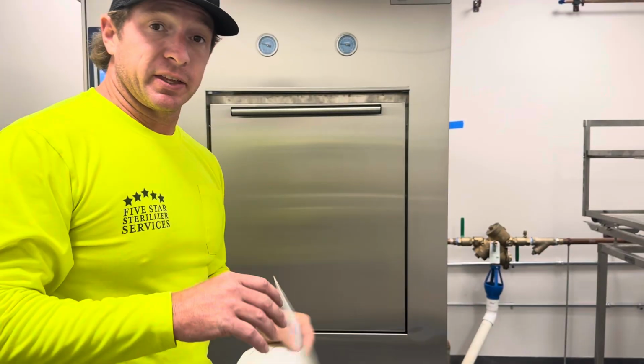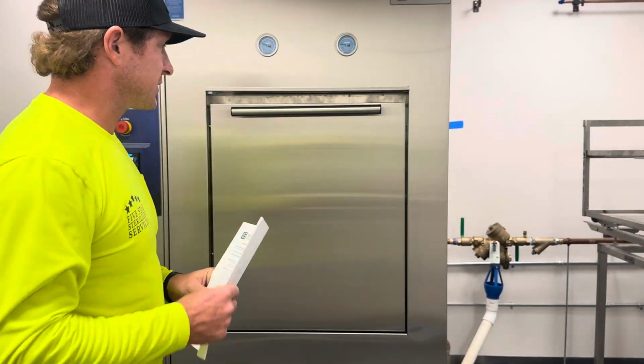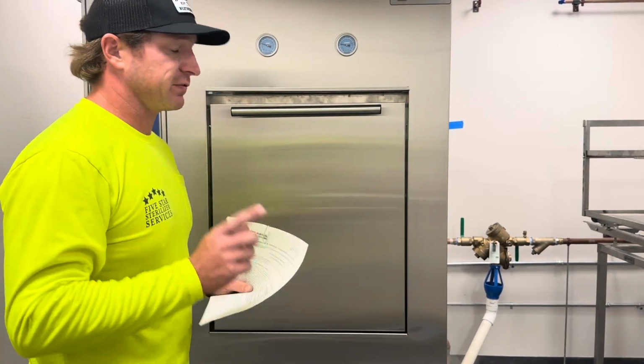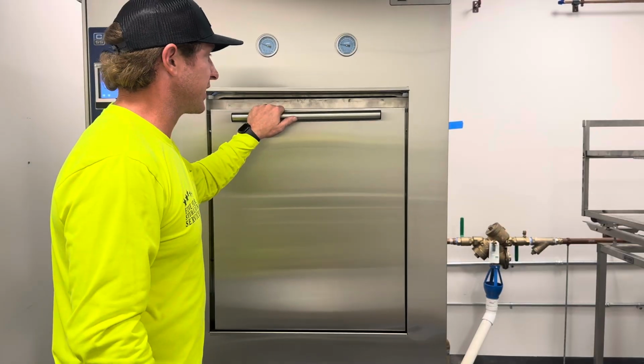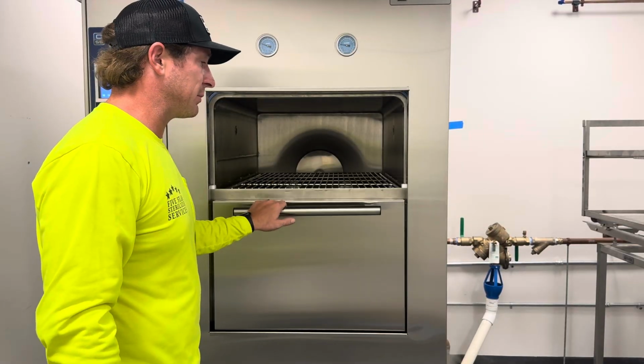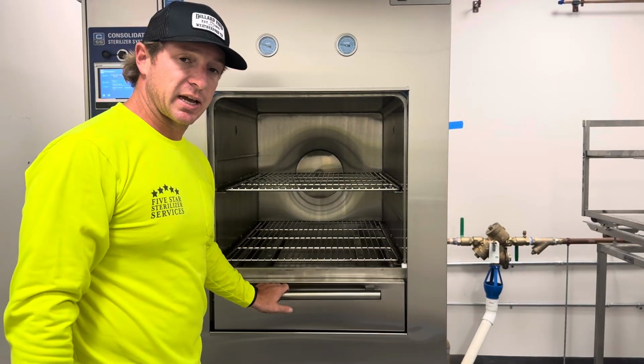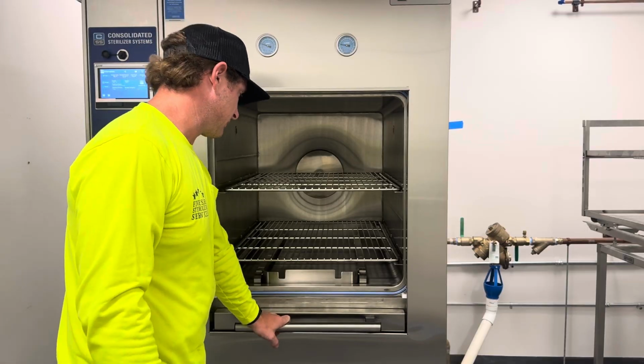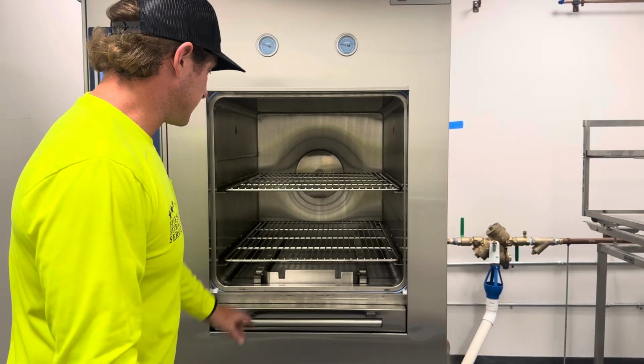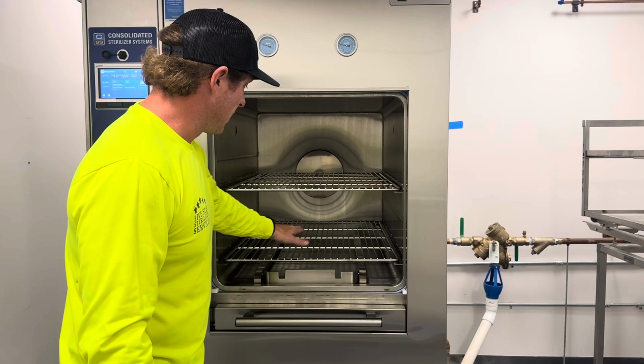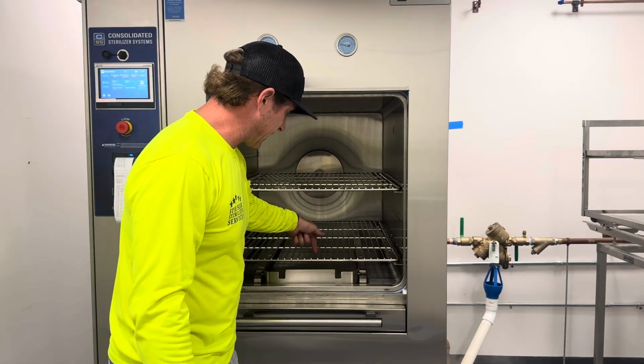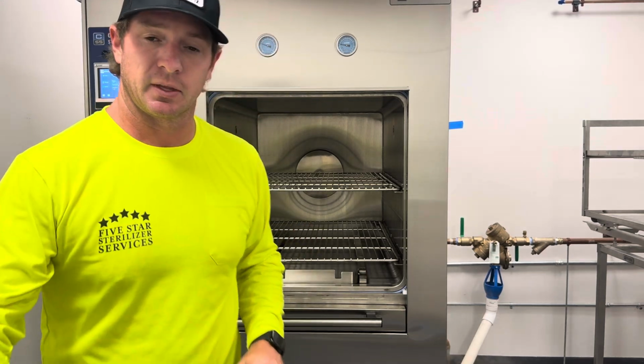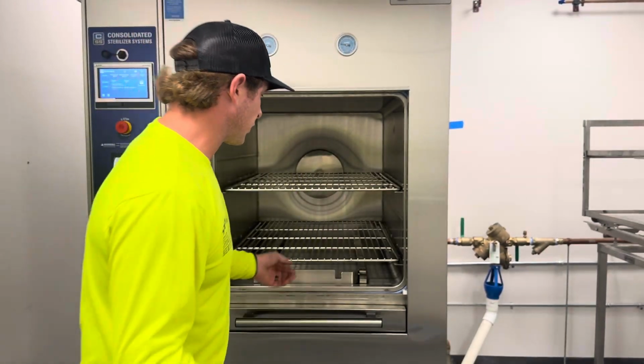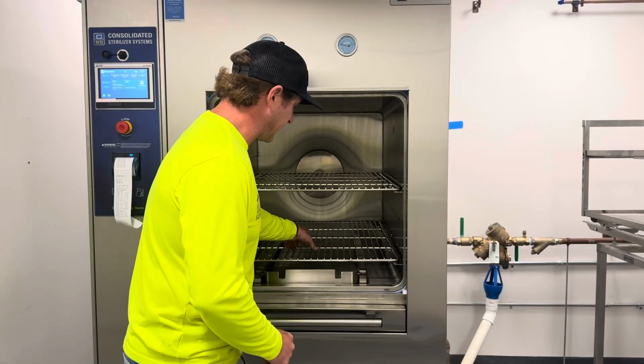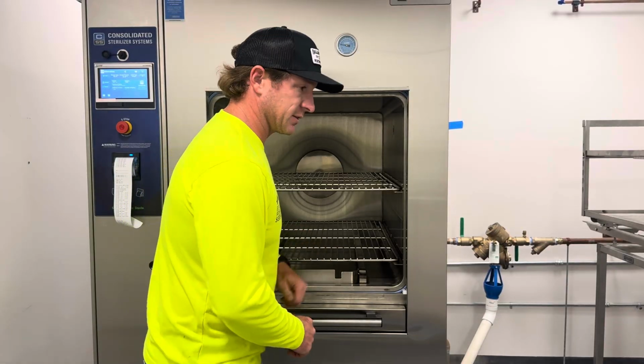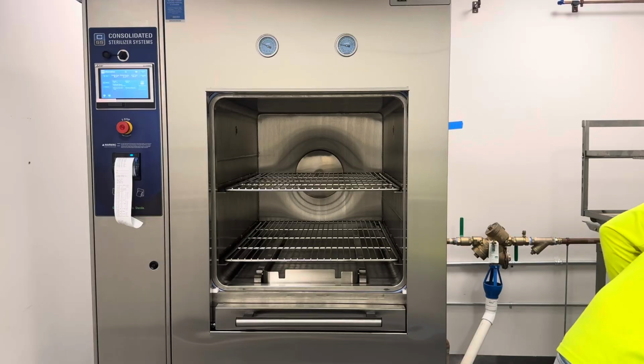Let's get started with the two most important things for this autoclave. The first most important thing is the daily requirement for the users to check the chamber drain strainer. The chamber drain strainer is located inside the chamber below this bottom rack right in the center of the chamber. It is the user's requirement or responsibility to remove this. Sorry, this machine is hot.